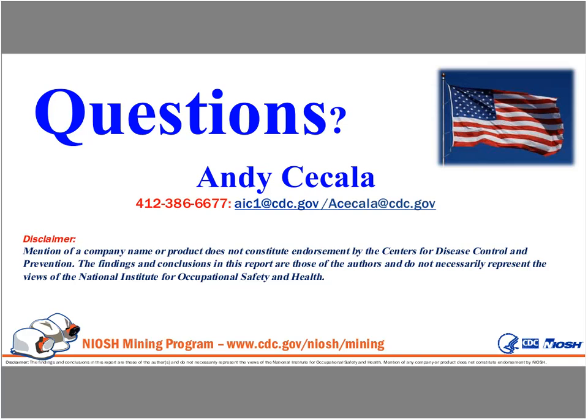Great. Okay. All right. One final question. Have you developed any guidelines on how often the MERV 16 filters need to be changed based on outside dust concentrations, similar to what filter manufacturers do for home HVAC filters? Well, again, from our testing, because every application is different, you could have a piece of equipment operating in an outside concentration of 10 milligrams and one at the same location operating in an outside concentration of 50 milligrams, five times higher.